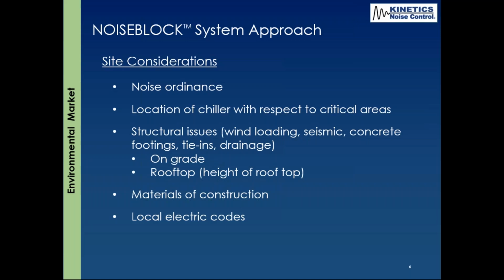The questions we always ask first: what does the site look like? Is the equipment—in this case an air-cooled chiller—on grade or on a roof? That matters because if it's on a roof, based on local IBC code, we'll have different requirements for restraint and structural supports. This particular job was on the East Coast, the coastline of North Carolina, so we had to consider IBC code and hurricane force winds. Luckily, it was on grade.